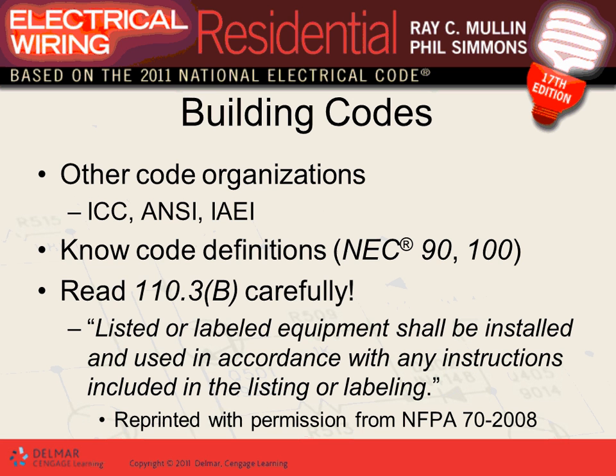There's one important thing: Article 110.3. Be careful—it says listed or labeled equipment shall be installed and used in accordance with any instructions included in the listing or labeling. For example, a GFCI receptacle—if you look at its listing, it says it has to be tested monthly. So how do you test it if you don't have access to it? If you put the GFCI receptacle right behind a big plasma TV, do you really want to move that entertainment center to test it? Now it's not readily accessible, and you've violated the listing and labeling of the equipment.